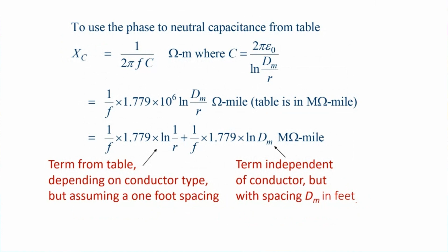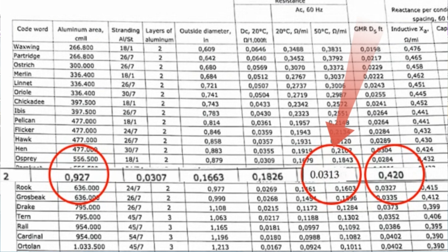What does this mean? Let's take an example: Dove - one conductor with this name, and I'll enlarge the information for this conductor. This is the data sheet. There's a code, this paired code name for the conductor, and these are the information. I enlarge it, which shows first 0.927 is the diameter of the conductor. And also you can see there, GMR. For this conductor, GMR is 0.0313 - geometrical mean radius from the data sheet, you can see it here. 0.0313, this is GMR, geometrical mean radius.